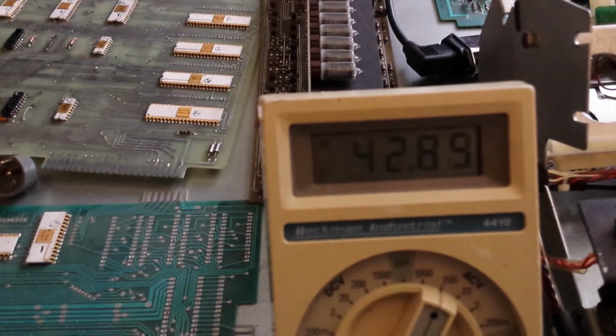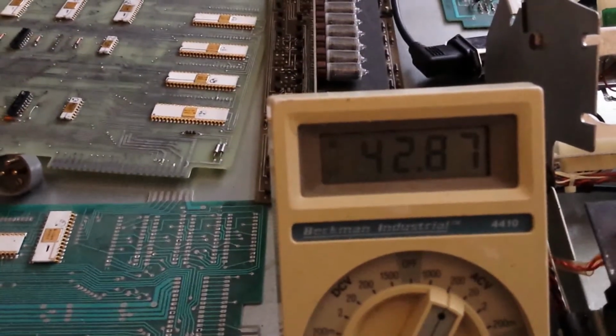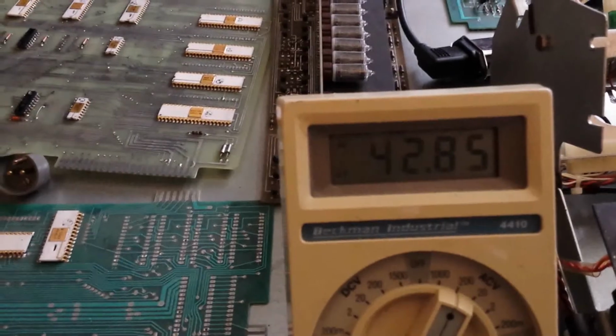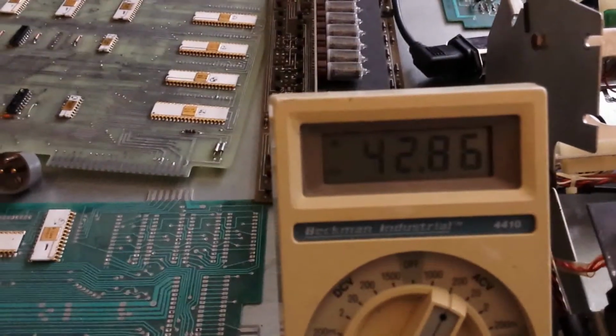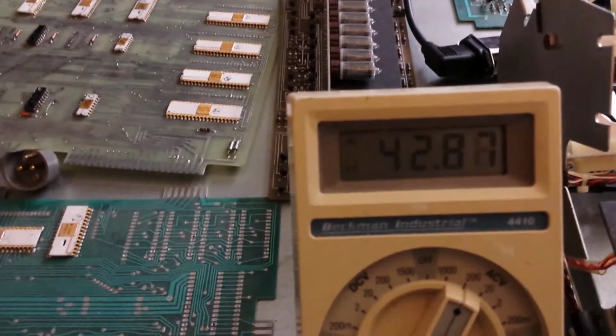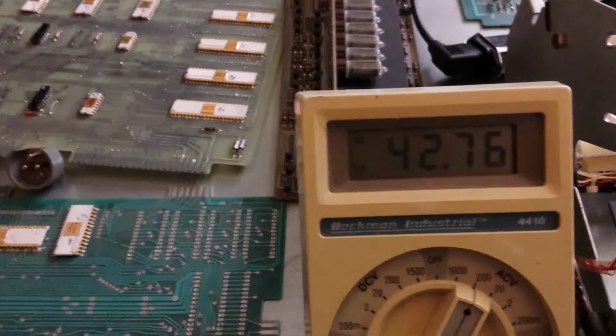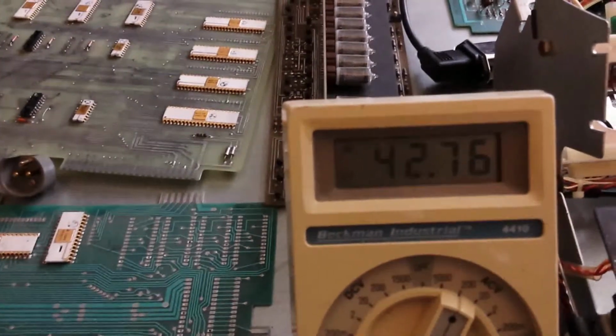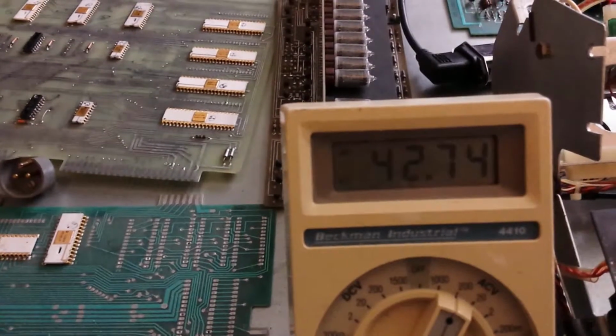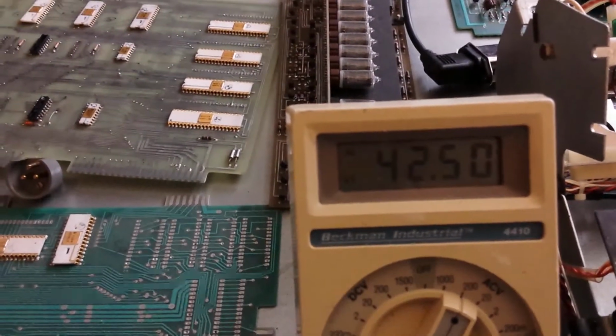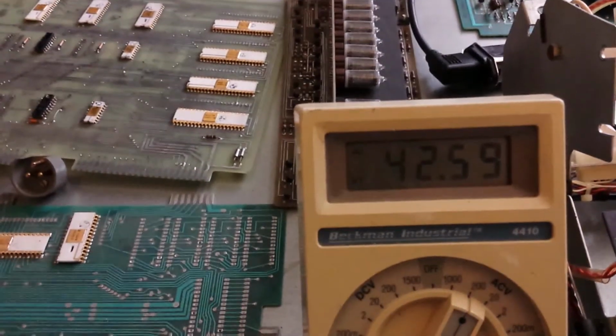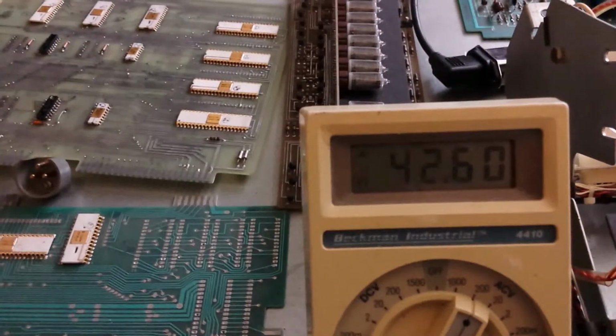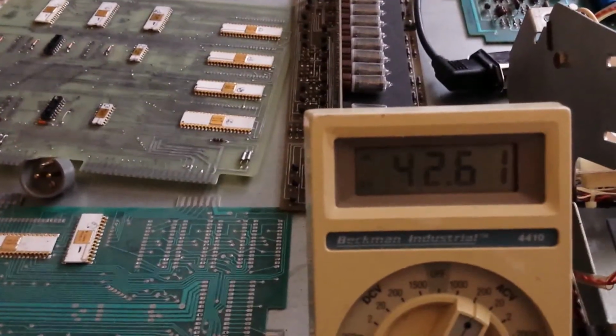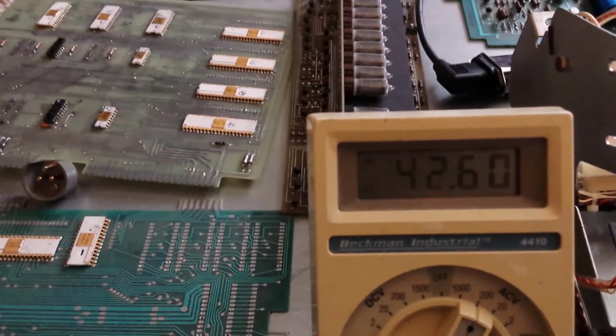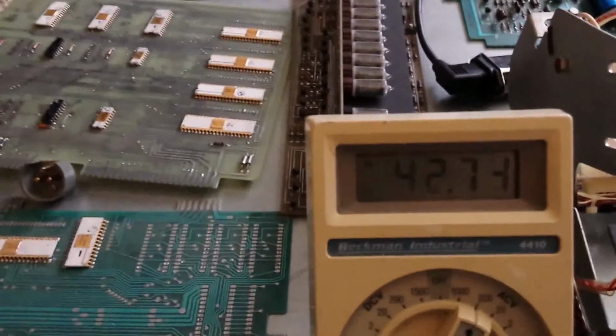They may be expecting the voltage to drop from the output of this transformer once it's loaded down. I don't really want to put a load on this right away until I know the power supply works. I don't want to crank this thing up right away and just throw everything back together and flip the switch. So that's the advantage of the Variac, is that I can make sure I don't run too high a voltage on any of these caps past their rating as I slowly crank this thing up.